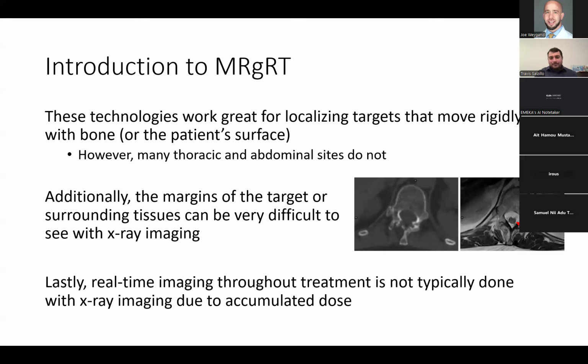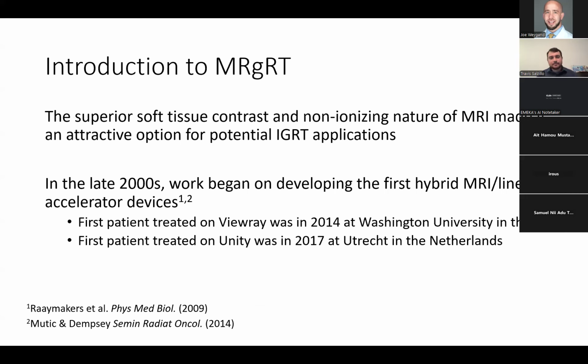The last thing that MR offers that X-ray doesn't is that real-time imaging typically is not done with X-ray. You can do fluoroscopy-based image guidance where you're constantly acquiring X-rays to see if the target is moving or if the patient moves. But that, of course, adds additional dose. And sometimes you can't acquire fluoroscopy at the same time as you're beaming on. Some systems allow you to, but not everyone does. It's just not really typically done unless you are specifically looking at a target that moves, such as a thoracic treatment. But at the end of the day, you can achieve this level of real-time imaging a lot easier and a lot safer with MR than you can with CT. So that's the motivation of why MR would make a really good onboard image guidance tool.